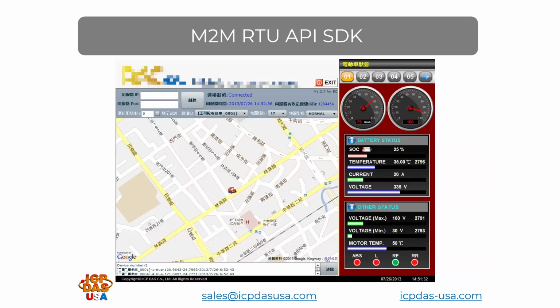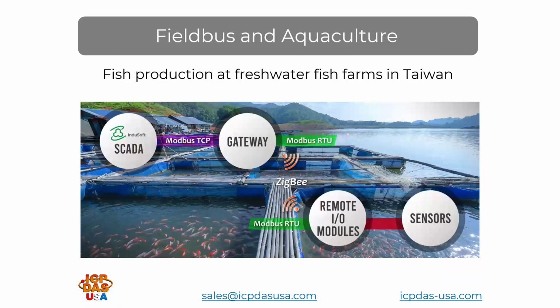For the Fieldbus portion of the system, we're using two of our Modbus RTU analog input modules. One is an 8-channel high-voltage analog input module, the M7017R A5G, to monitor the bus battery voltage, and an 8-channel thermocouple input module, the M7018RG, to monitor the battery's temperature.